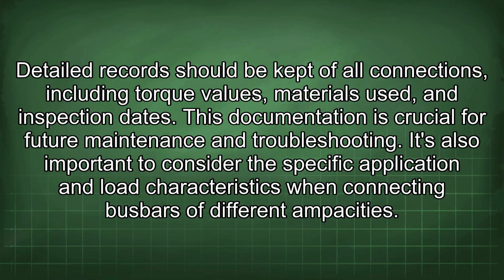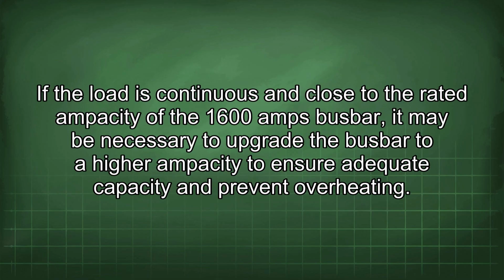It's also important to consider the specific application and load characteristics when connecting busbars of different ampacities. If the load is continuous and close to the rated ampacity of the 1600 amps busbar, it may be necessary to upgrade the busbar to a higher ampacity to ensure adequate capacity and prevent overheating.